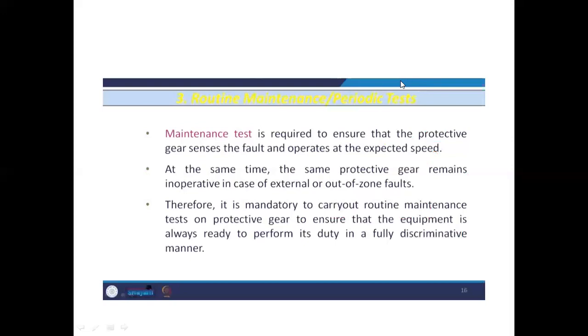Okay, and in the sequence of commissioning and testing of the relays, we have the third one, that is the routine test, or we can also call it the periodic test, because we have to perform these tests periodically. That is why these are called the routine test or the periodic test. These tests are carried out to check its operation for maintenance purposes.